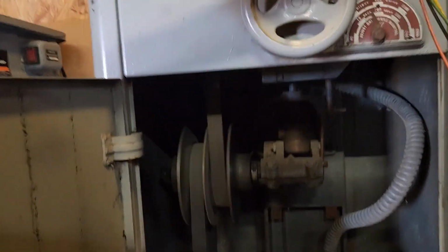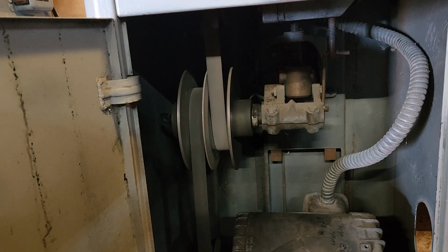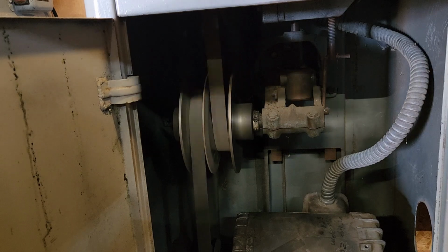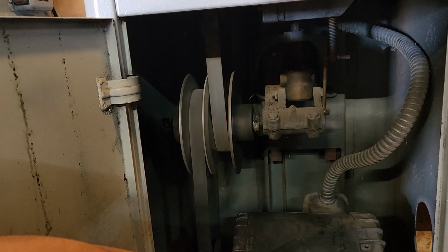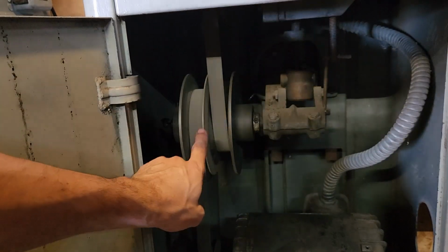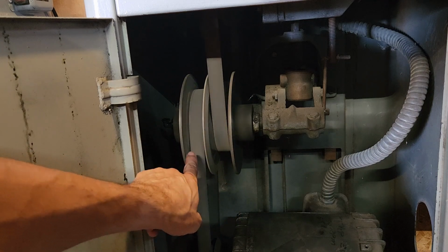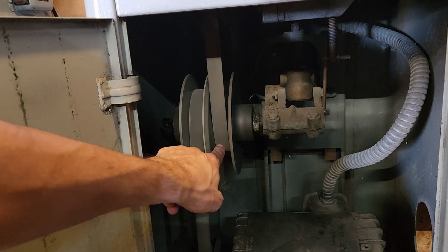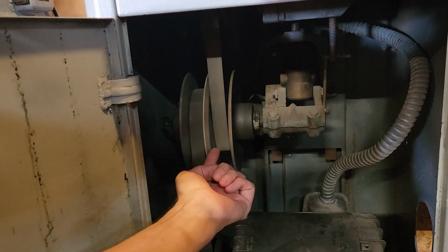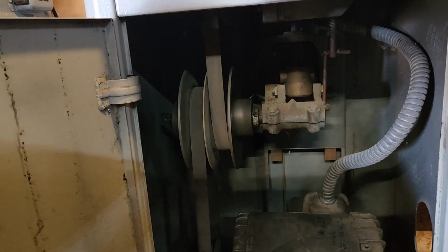And I don't know if you can tell, but when you change that speed, the belts, it's kind of a two-pulley system. The motor is running at a continuous speed. This belt's moving at a continuous speed. But when you move this, the center part of the pulley is moving left or right, which either forces this belt out further and this one in further, so that slows it down. So if I go back the other way, you'll see this belt move out and this belt move in. So you're effectively changing the pulley size.